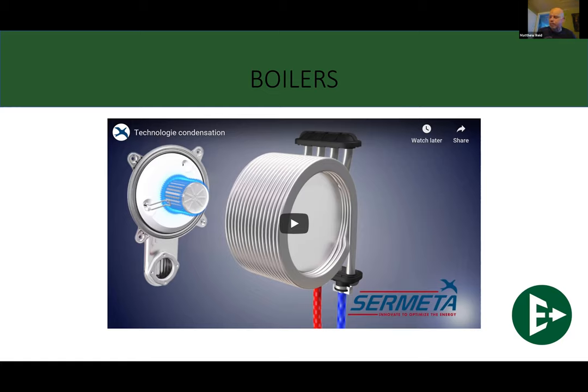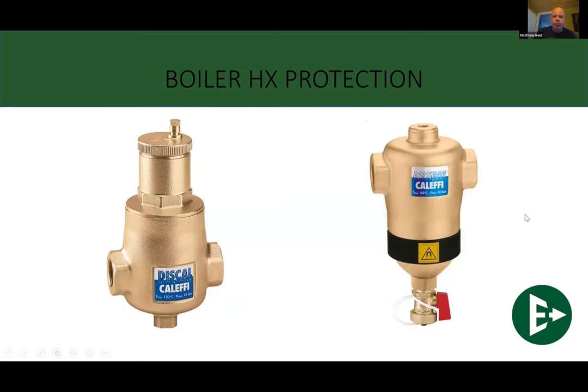In some cases it is pretty unavoidable to get at least some coming back. But this heat exchanger is just a little bit more prone to being susceptible to that type of application, where if you do have any recirculation of flue gases, you're definitely going to get the coffee grinds in the bottom. It's pretty easy to clean up, doesn't take much, but these heat exchangers really need to be cleaned definitely once a year. Fire tube, maybe a little bit less often, but because these ones are more susceptible to that, definitely clean them once a year. Okay, up here and check for questions.